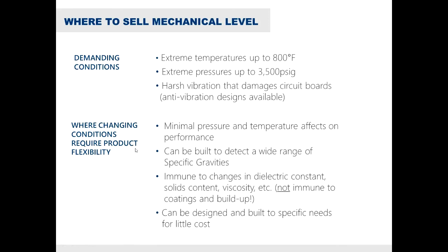Where changing conditions require product flexibility — processes that frequently change temperature and pressure — a float and displacer-type technology has minimal effects on performance from those process changes. Whereas, say, a differential pressure transmitter measuring level in the tank would give a false reading if temperature and pressure change, since SG will actually change. This buoyancy-type technology is also immune to changes in dielectric constant, solids content, viscosity, and similar factors that affect guided wave radar or technologies relying on the dielectric of the process.